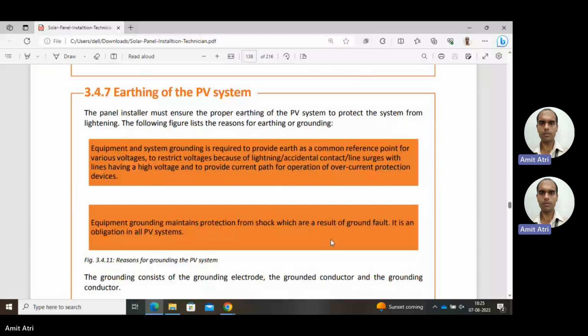First reason: equipment and system grounding is required to provide earth as a common reference point for various voltages, to restrict voltage because of lightning, accidental contact line surges with lines having high voltage, and to provide a current path for operation of overcurrent protection devices. So why do we need proper earthing? Because the over voltage and over current which is induced in our system should be diverted towards the ground, towards the earth. So this is the first reason for providing earthing.